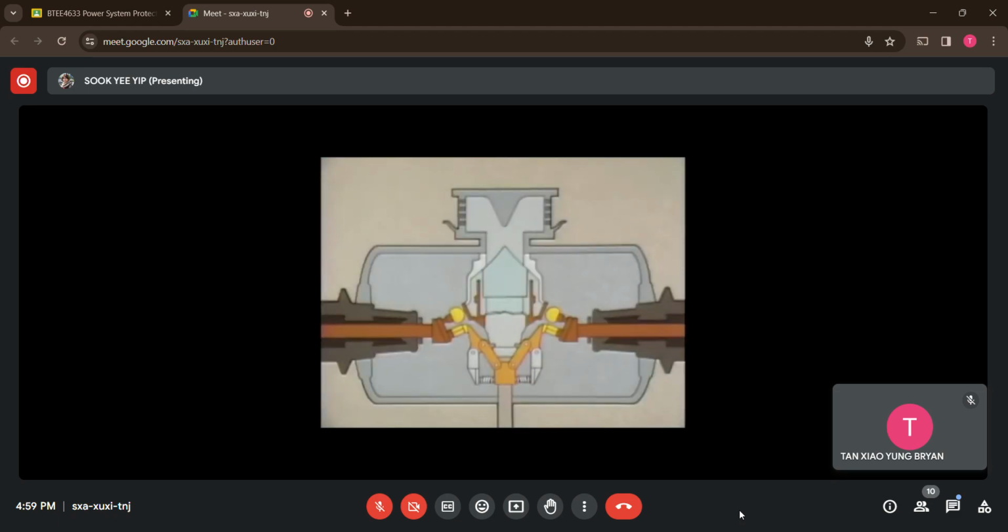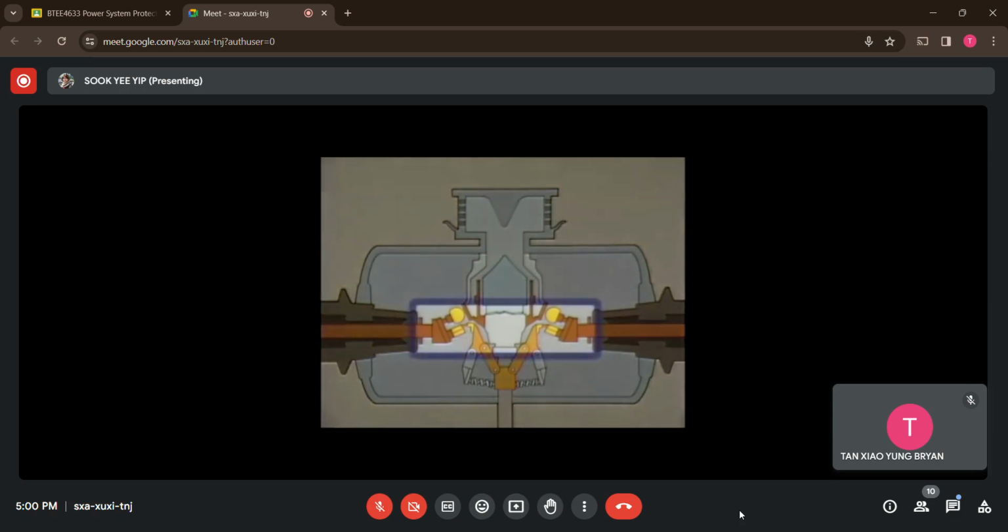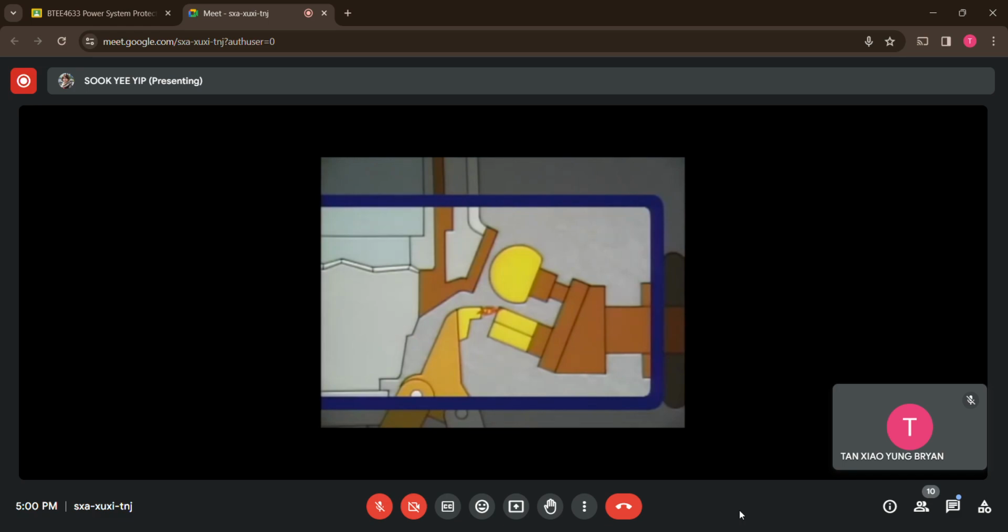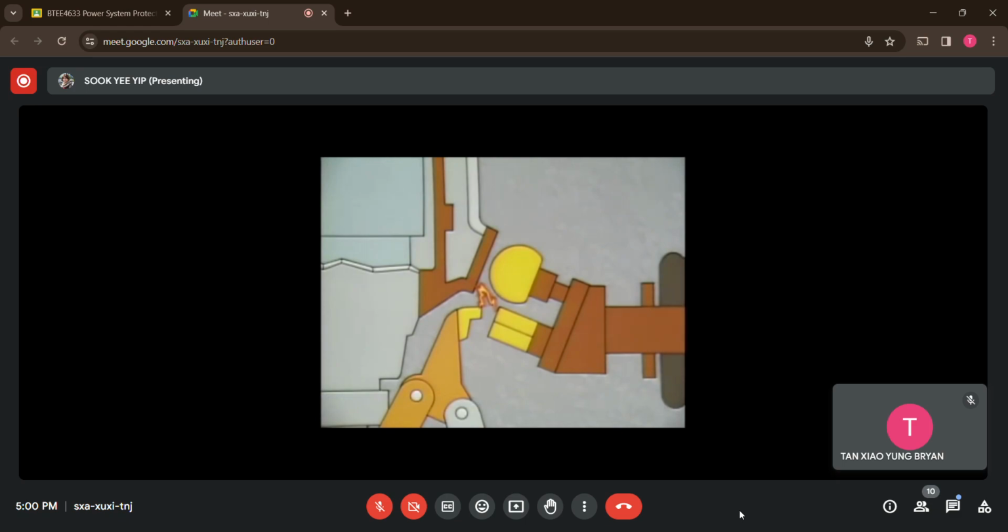Let's go back to the breaker in the closed position to see what these features are and how they work. One feature is the blast valve. When the breaker is closed, the blast valve blocks the arc chutes. As the contacts separate and arcs form, the blast valve moves, uncovering the arc chutes. When the chutes open, the pressurized air in the breaker head blasts through the arcs and through the arc chutes to atmosphere. The blast of air helps cool the arcs and at the same time forces the arcs away from the arcing contacts and toward arcing probes and arcing rings.